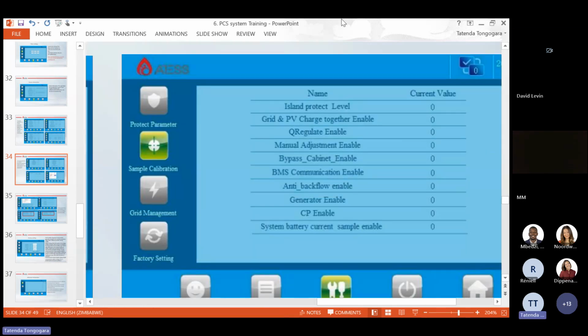And then these settings are just the same as your HPS. So most of the settings on the PCS are the same as the ones on HPS. Your grid and PV charge enable, you have to enable it. Anti-backflow enable, you set to 0 if you want to export, and you can set the export limit. Generator enable, if you have a generator, you enable it. PV inverters, you enable your CP.